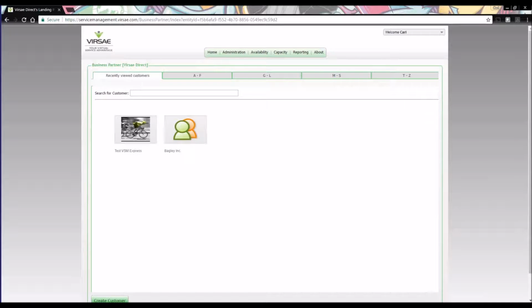We need to have the availability options set appropriately. That basically determines where the alarms will be sent, whether they're going to go to the service desk or whether they're going to go to the call-out lists or both, and whether they're going to get notified as email or SMS or both. We also need to have an alarm rule and a workflow associated with it as well.